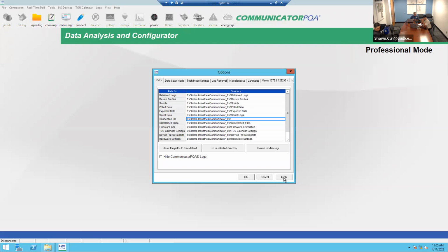From an energy perspective, I just want to get the totalized energy consumption and then the demand over to the energy information system. That way we'll have a picture of how much energy we're consuming and what the instantaneous demand is. Most of the data requests that we get externally are for those two items. They want to know consumption, and if they're doing load studies, they're going to want to know what demand is. Gotcha. Yep.